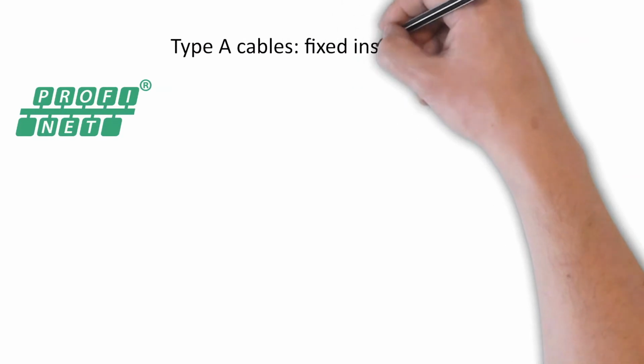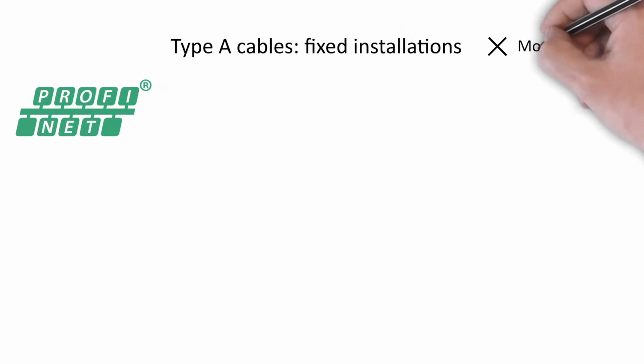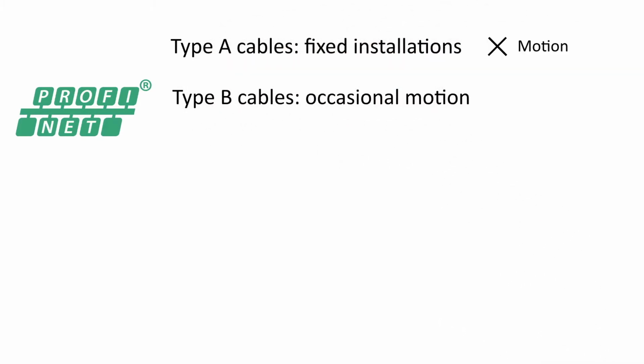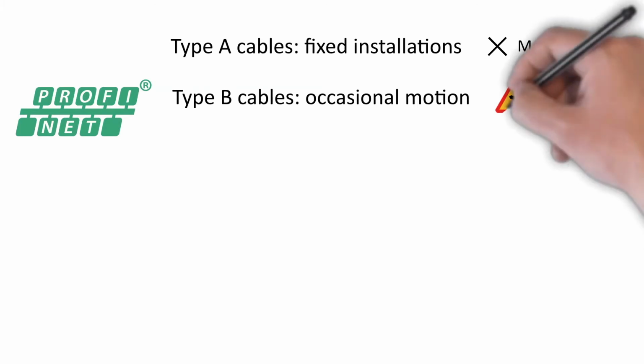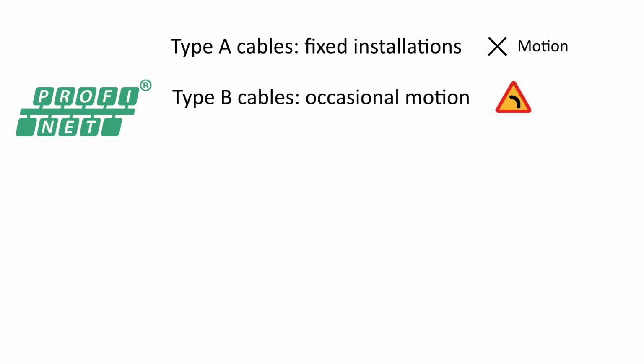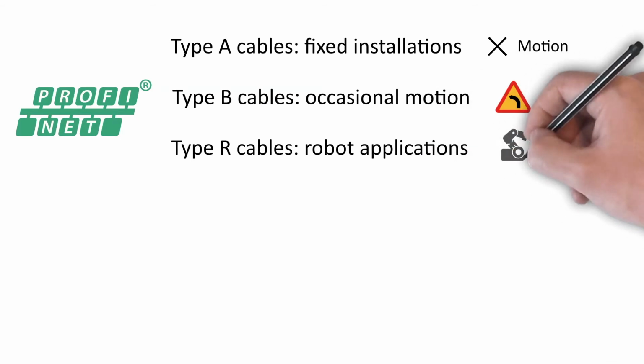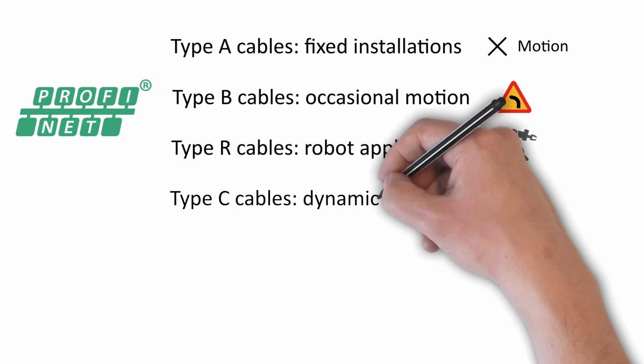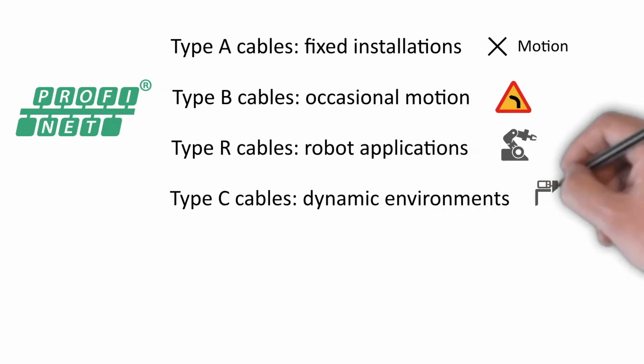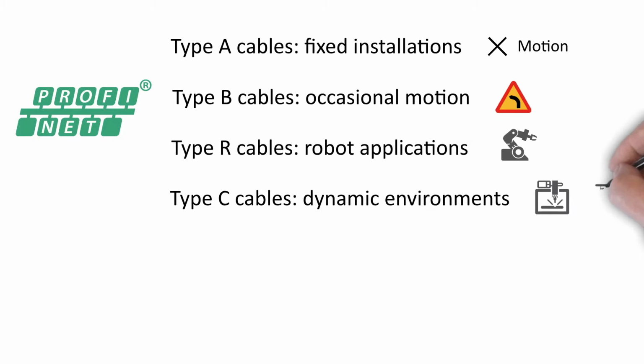There are 4 Profinet copper cable types: A, B, R, and C. Type A cables are for fixed installations. They should not undergo motion after commissioning. Type B cables are for installations where flexing may be present. These cables can withstand occasional motion or vibrations. Type R cables are for robot applications and are tailored for that specific usage. Finally, Type C cables are for other specialized applications. They can withstand movement and dynamic environments, for example, rotary machines.